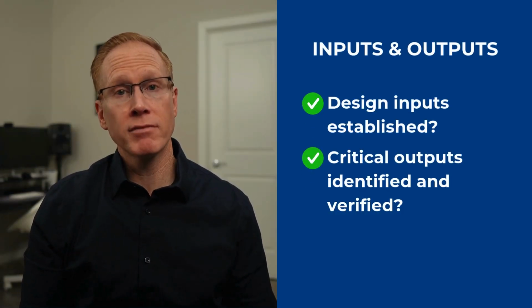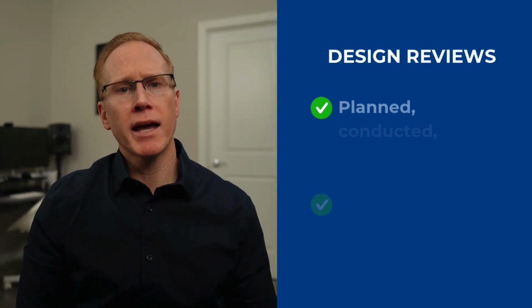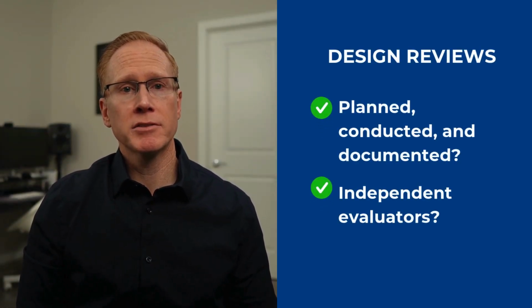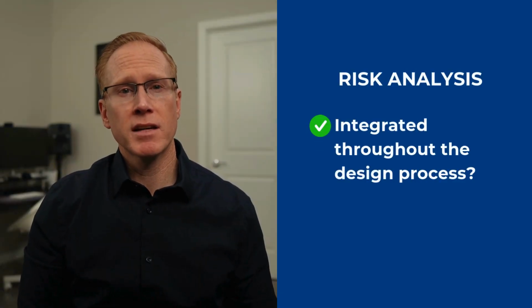Inputs and outputs. Are design inputs established and are critical outputs identified and verified? Acceptance criteria. Were criteria set before verification and validation activities began? Design reviews. Are reviews planned, conducted, and documented with independent evaluators? Risk analysis. Was risk analysis integrated throughout the design process?